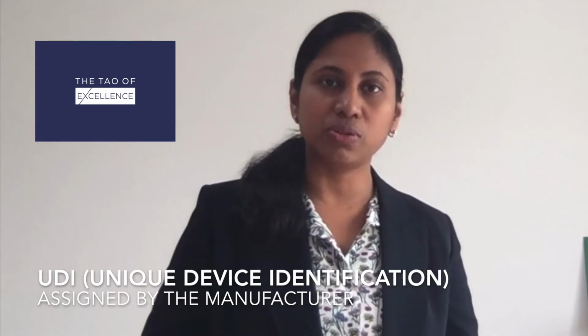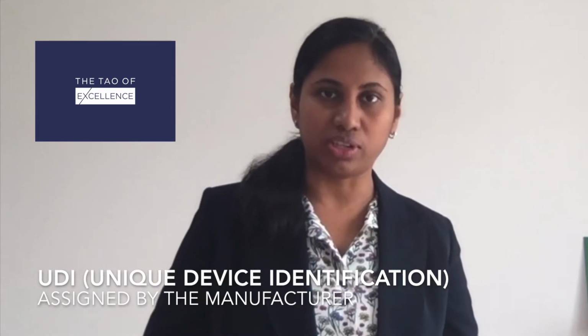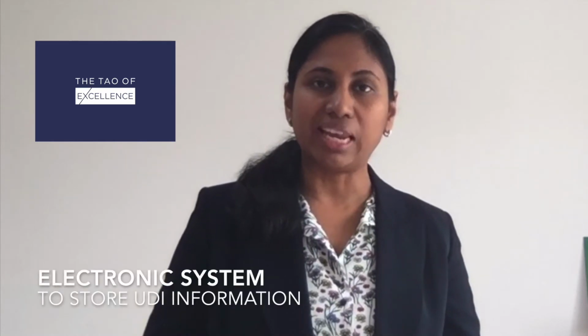The importer has to check if the device has been labeled in accordance with the requirements of this regulation and if the device is accompanied by the IFU, the instructions for use. Wherever applicable, he has to check that the device has a UDI assigned by the manufacturer. The importer must have provisions to electronically store the information on the UDIs.